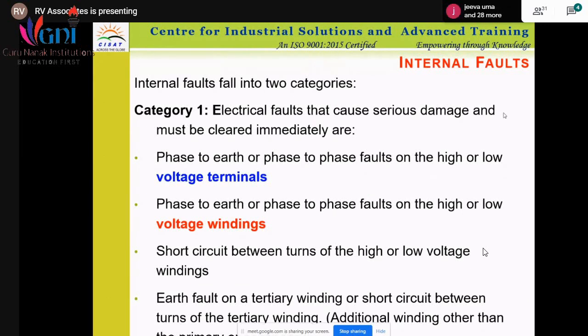These are the internal faults. Internal faults are normally categorized in category 1 and category 2. So it's a winding fault. Winding can be a winding to winding fault. So we say the phase to phase fault, line to line fault, or phase to earth fault. It can be at the terminal as well as the winding, means internal windings, or it can be at the terminals. So those categories are there.